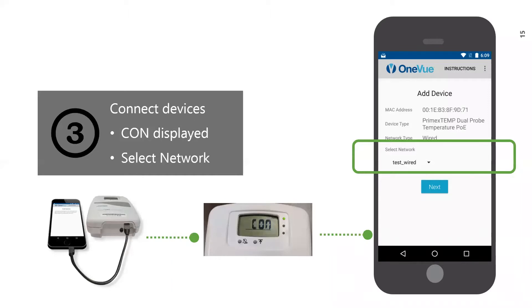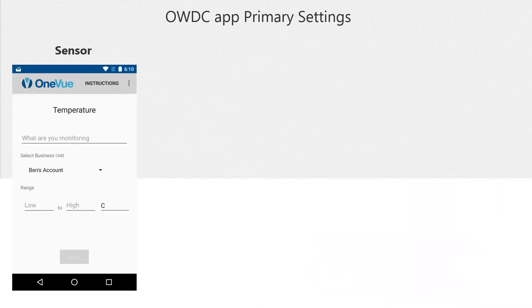Select Next to configure its other primary settings. You will configure or edit the device's primary settings, which vary by device type. For a PrimeX temp or IAQ sensor, you will provide the device's assigned network — be sure the network profile is already configured in OneVue. Then you will set its monitored asset, which is what the sensor will be monitoring. You can either create a new monitored asset or enter the exact name of the monitored asset already in OneVue.